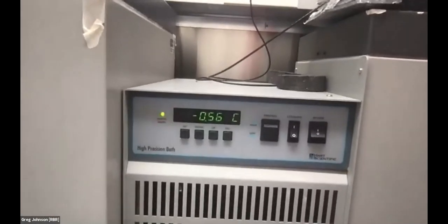So these baths will have set points on them. For instance, looking at a bath here, it says it's at -0.56 degrees. The one adjacent is at 9.37. But we don't actually trust those temperatures. Those temperatures are just indicative, and the actual temperature in the bath might be different by half a degree or so.